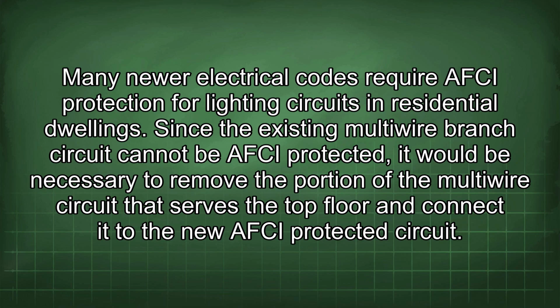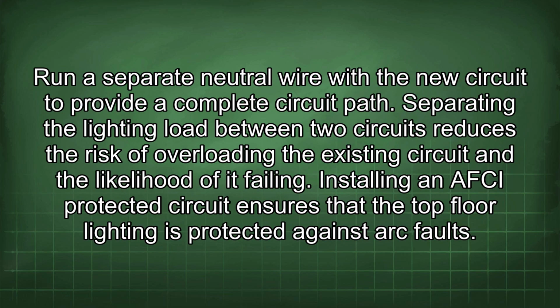Since the existing multiwire branch circuit cannot be AFCI protected, it would be necessary to remove the portion of the multiwire circuit that serves the top floor and connect it to the new AFCI protected circuit. Run a separate neutral wire with the new circuit to provide a complete circuit path. Separating the lighting load between two circuits reduces the risk of overloading the existing circuit and the likelihood of it failing. Installing an AFCI protected circuit ensures that the top floor lighting is protected against arc faults.